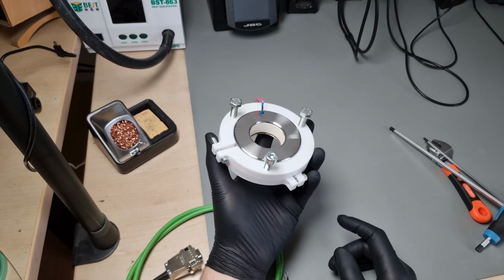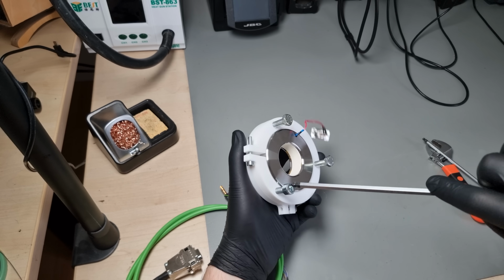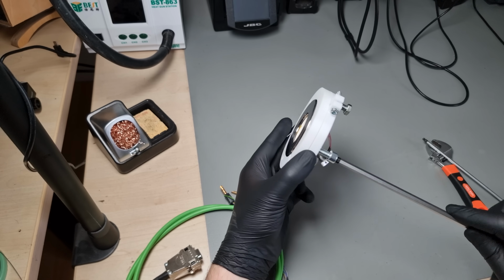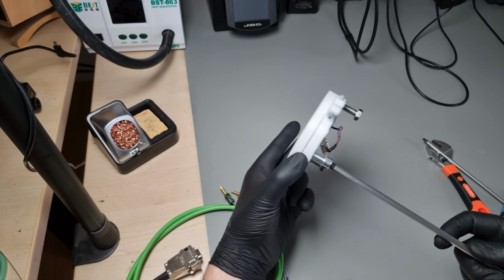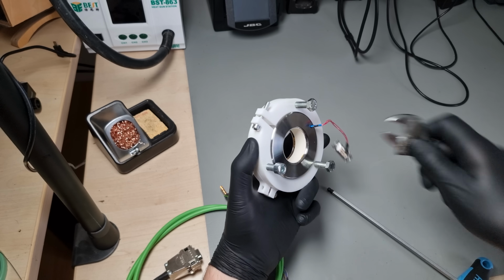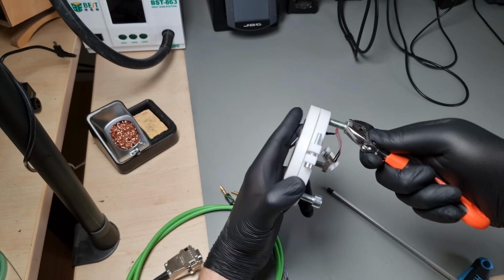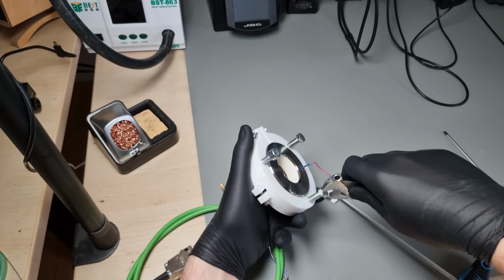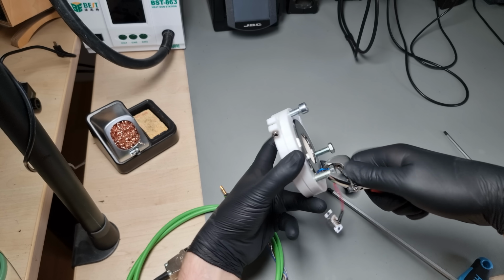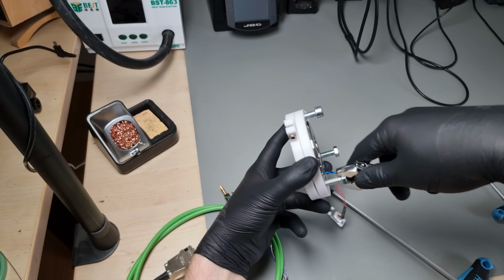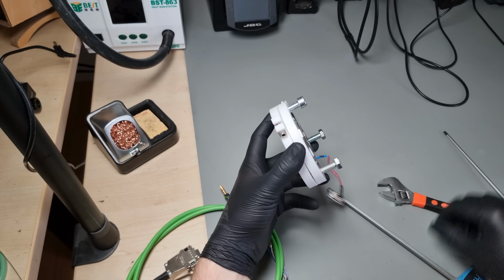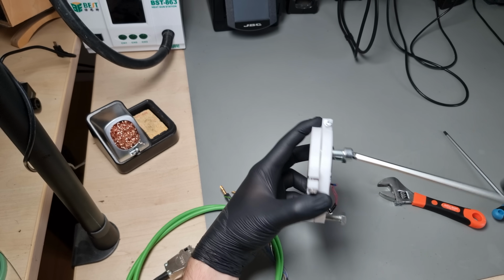In order for these to detect the exact point where zero flux density occurs, where the primary and secondary ampere-turns are exactly equal, the internal detector depends on the highest magnetic sensitivity possible. For that to not be disturbed by the surroundings or the earth, they need extremely effective magnetic shielding, which this bright and shiny bare metal shell is part of.